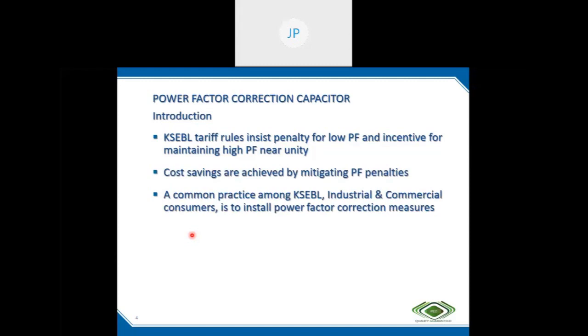It is a common practice among utilities and consumers to install power factor correction measures. What are the reasons for the low power factor? As we know, it is inductive loads, especially motor loads. They need reactive power also to deliver active power. Consumption of reactive power, of course, produces low power factor.